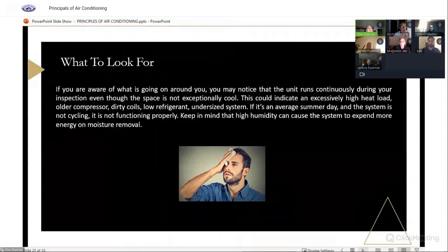So this slide talks about being aware of what's going on around you. You may notice the unit runs continuously during your inspection, even though it's not exceptionally cool. If I feel that way, or if I see a 3,000 square foot house and this tiny little condensing unit outside, I'll call for evaluation of it.